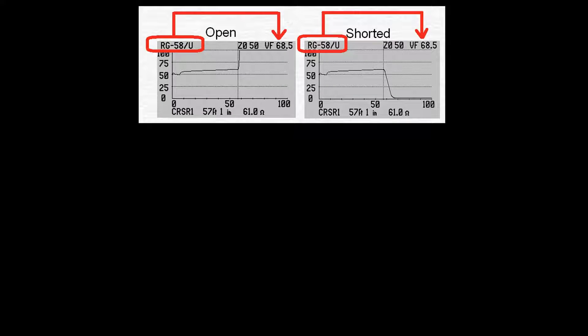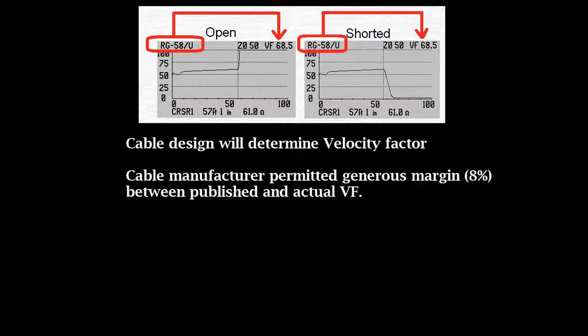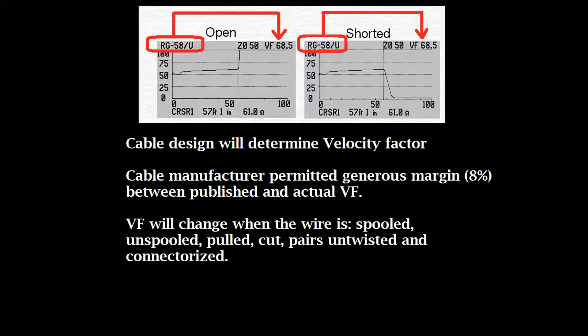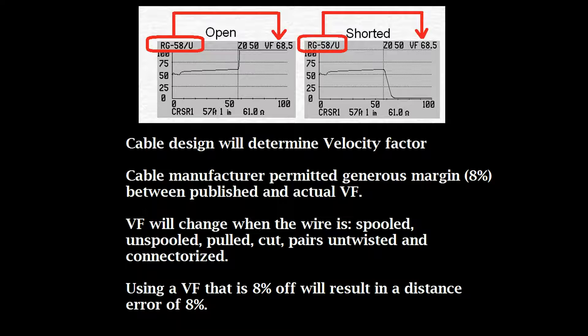Keep in mind, the easiest way is not necessarily the best way. Here's why. Velocity factor is determined by the design and the building of the cable. Cable manufacturers are permitted a generous margin between the published and actual velocity factor. Once the cable is built, simply handling the cable can change the velocity factor. So any error shown in the entered velocity factor will directly show up in your distance readings.